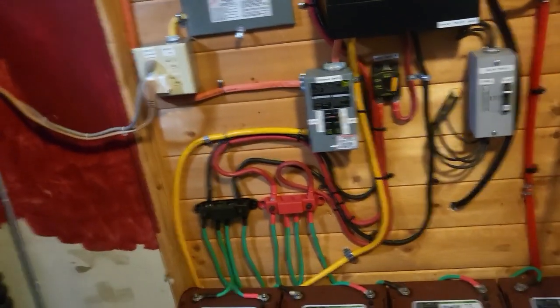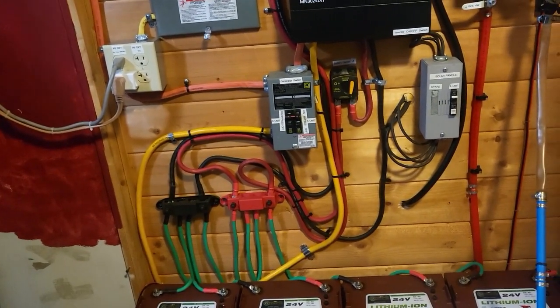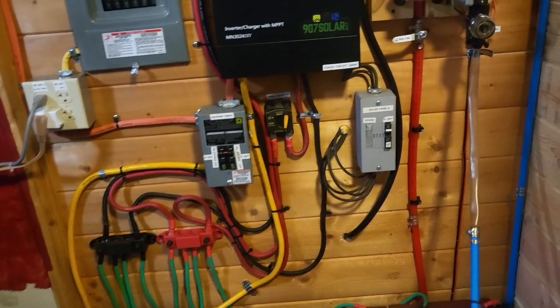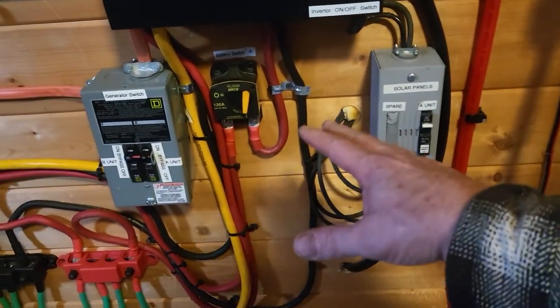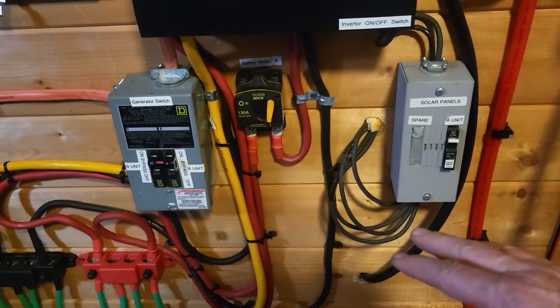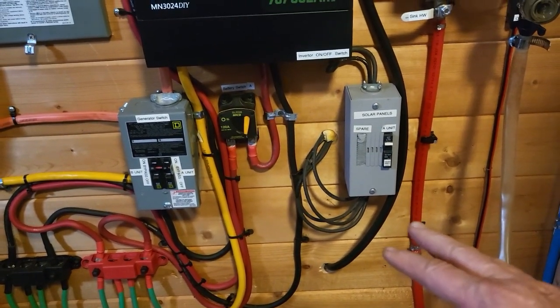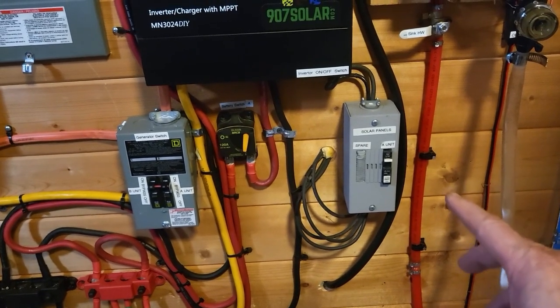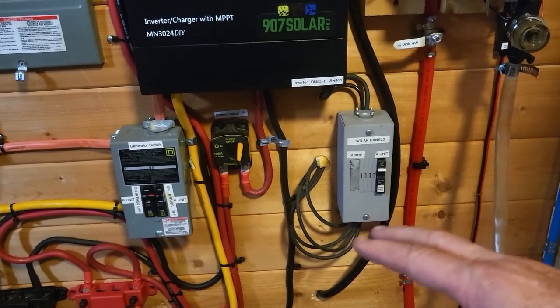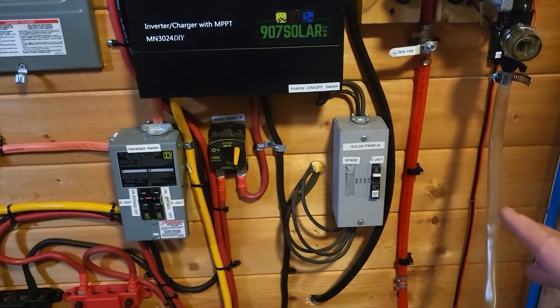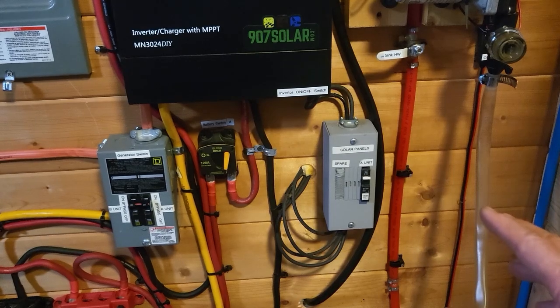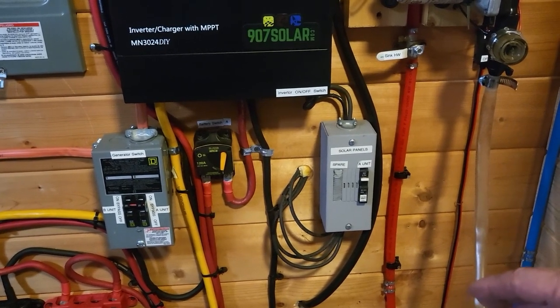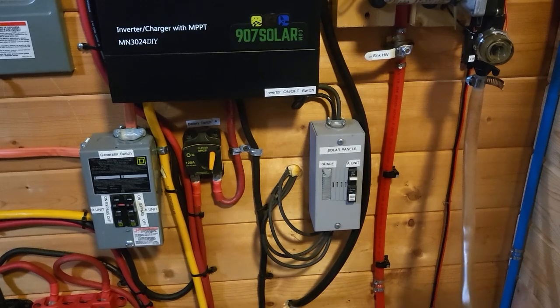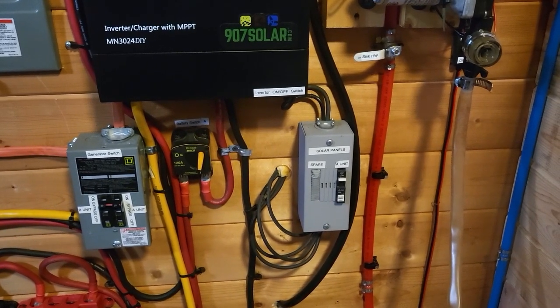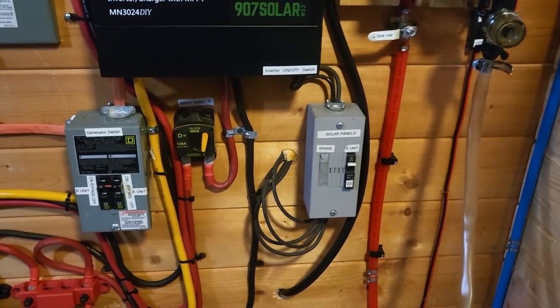Okay, it kind of starts here. As you saw, the solar panels outside in the array come in through the wall and run around the house, come in through here. I've got two separate lines, one for 2 panels and the other for 2 panels. I did that on purpose because, as you know, it's only going to draw what the weakest one is putting out. So if I've got one that's weak on one string, it's only going to put out so much, and on the other string it could be putting out more. So I'm trying to maximize on it.